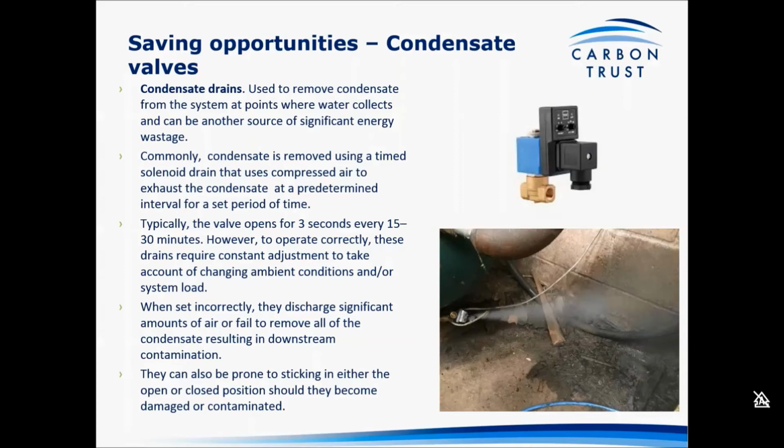That one on the bottom there, I think I took that photograph. That's at a sawmill, and that valve had just stuck open, and you can see from the oil on the ground and on the wall where the spray has been impacting on it, and that's been like that for weeks, if not months, and it was just ignored.